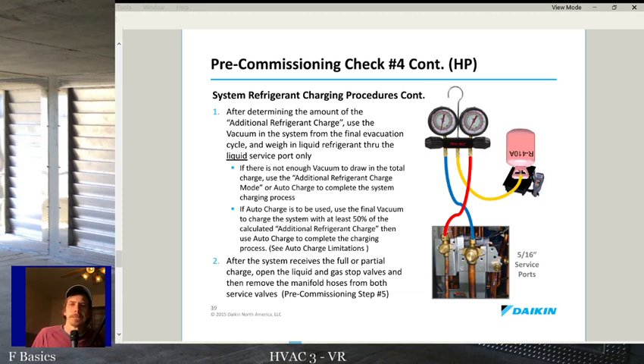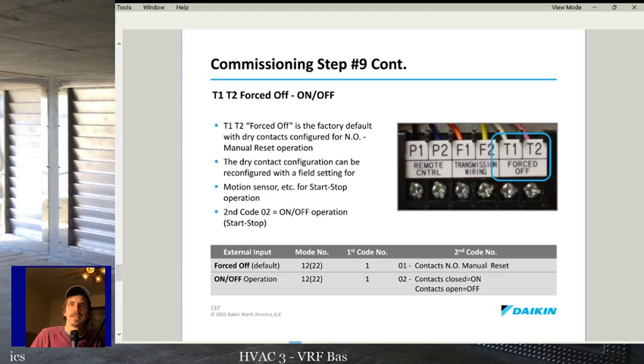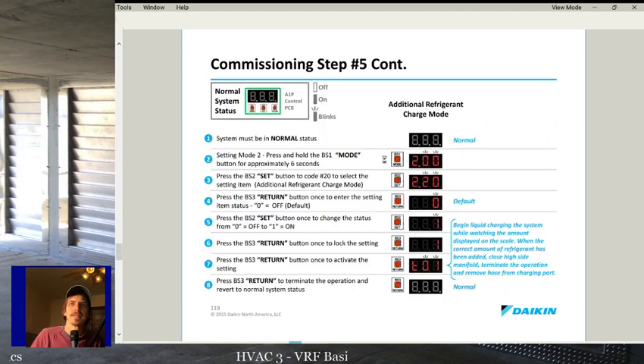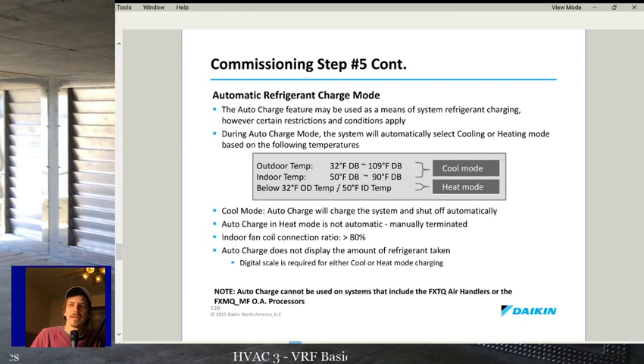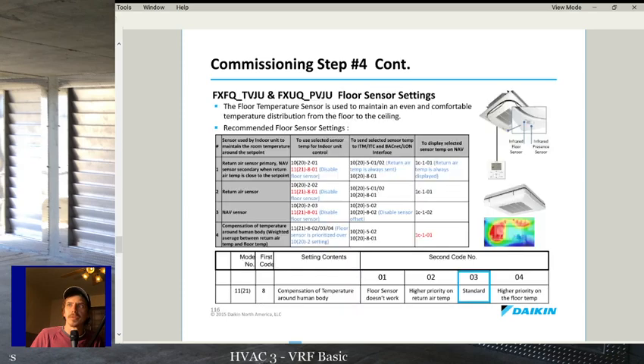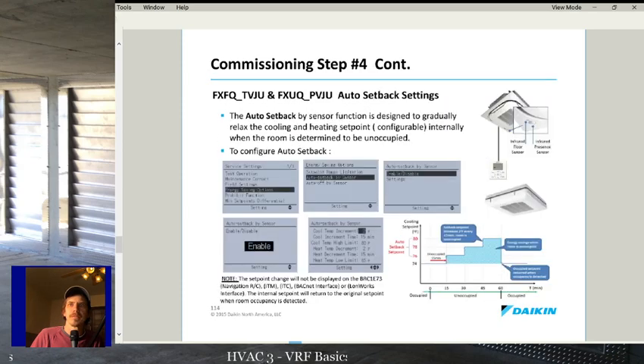But you do have to know the length of the line set and make sure you add enough charge for your length of line set. And as a matter of fact, there should be a slide on that. Let me see if I can find that before we wrap up. Let me see if I can find the slide, because this is another thing that basically stays the same on every system you're going to work on. Alright, these numbers, you have to add the same amount of refrigerant for line set basically no matter what system you're doing. Okay, it really doesn't make a difference.